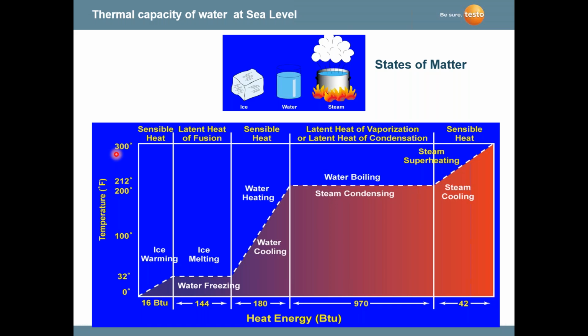So by looking at water, we can visualize easily that as we add heat to water, that's called sensible heat, because we can measure it. Something that we can measure is called sensible heat. As the temperature rises and we're adding more and more heat, it reaches a point where at 212 degrees and at sea level pressure, which is 14.7 PSI, you're going to see what we call saturation taking place. That means that the water, the liquid, and the vapor are changing state. In this case, liquid is changing to a vapor. And when we have that taking place, which happens in the coils, we have no temperature increase.